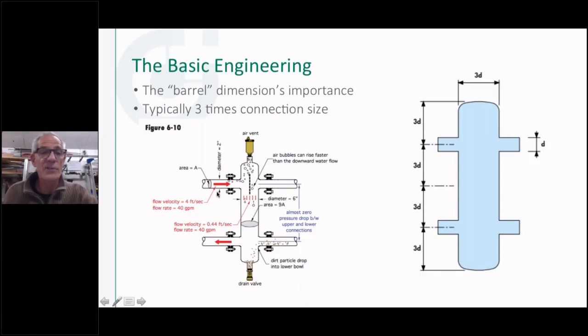If you look up the chart, you'll see it takes about a 2-inch pipe size to move 40 gallons a minute at about a 4 feet per second velocity. So the key to this is this chamber, the center portion here, let's call this the separator function, needs to be about 3 times the diameter of the pipe coming into it. So if you decide that you need 40 gallons a minute and you need a 2-inch pipe, then this barrel needs to be about 6 inches in diameter.